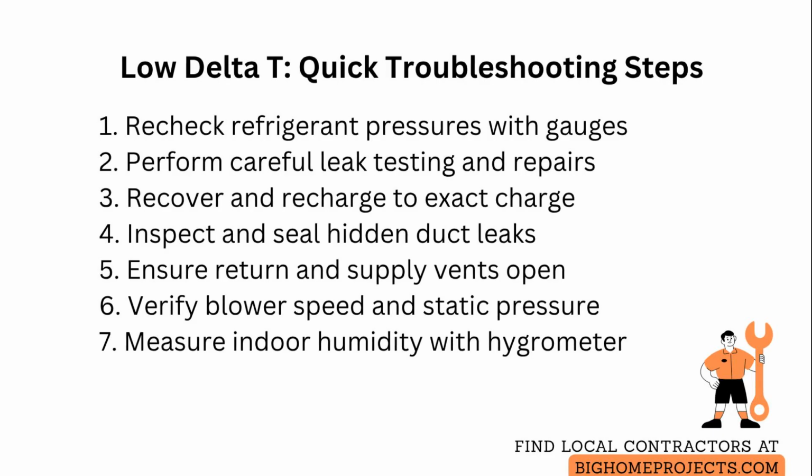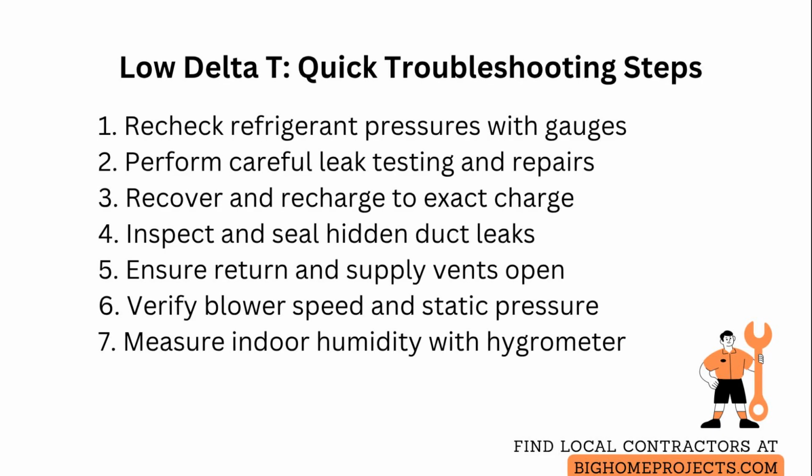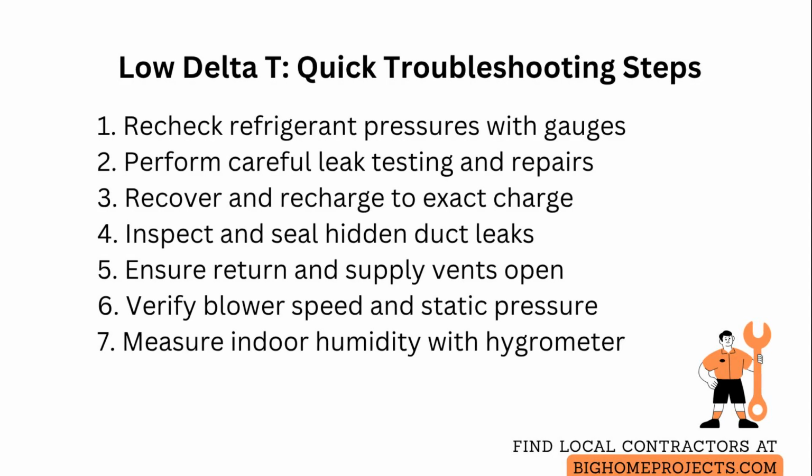If pressures are low, perform a careful leak test using a sniffer or soap solution and repair any leaks before adding refrigerant. Always recover and recharge to the exact charge weight when required.